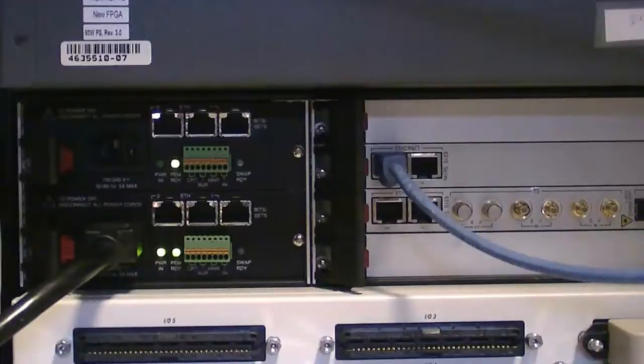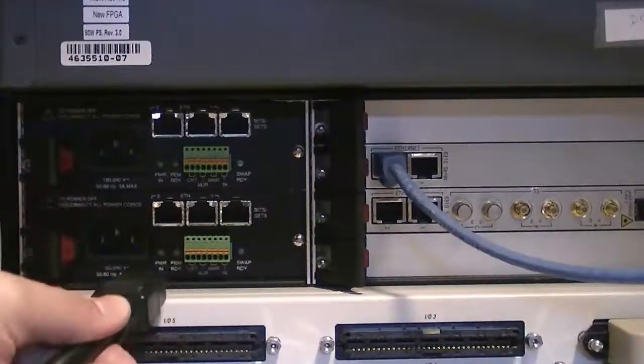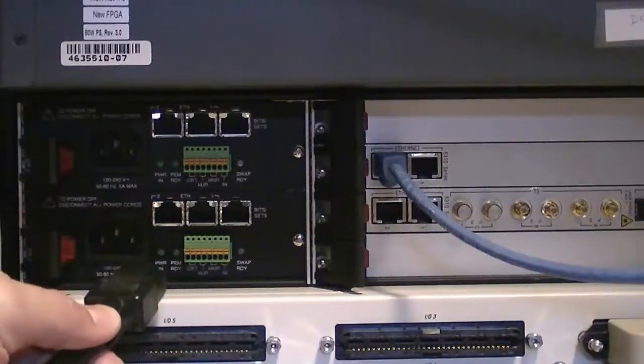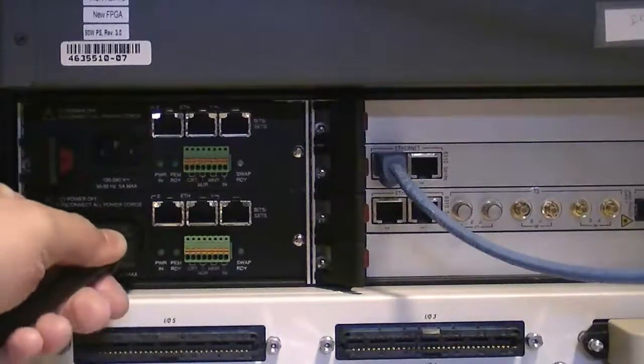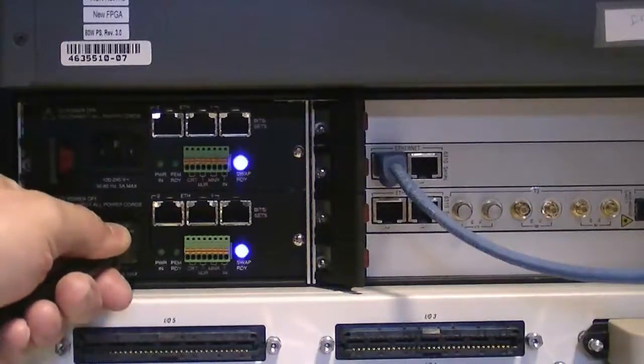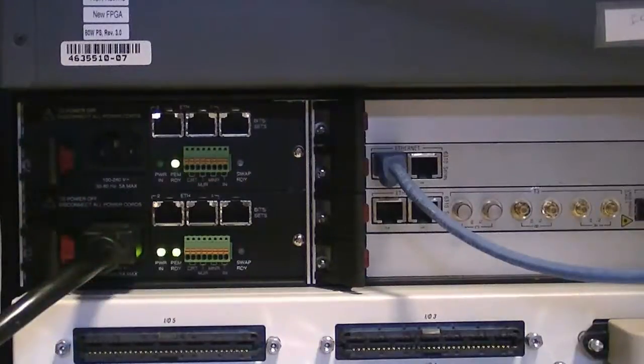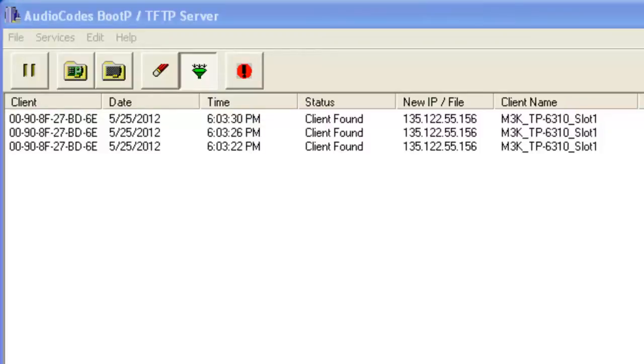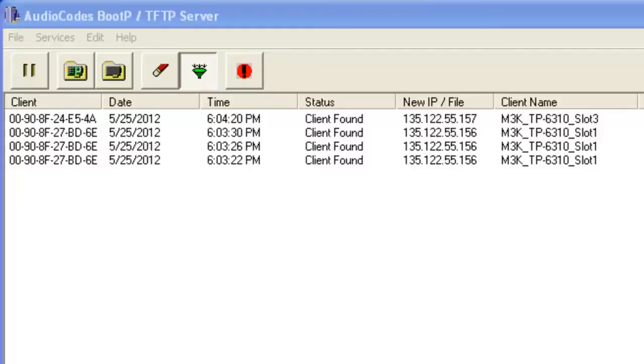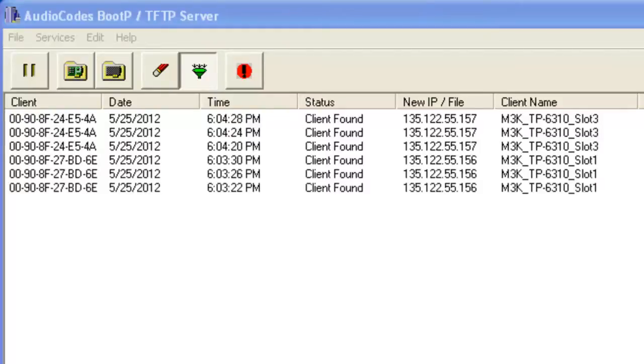Once connected to the standby board, physically reset the gateway again. With the slot 1 board having already successfully requested and received its network configuration information, the slot 3 board should send its BootP request within 10 to 20 seconds. However, if it does not, reset the gateway again. You see the slot 3 board request in the BootP application.